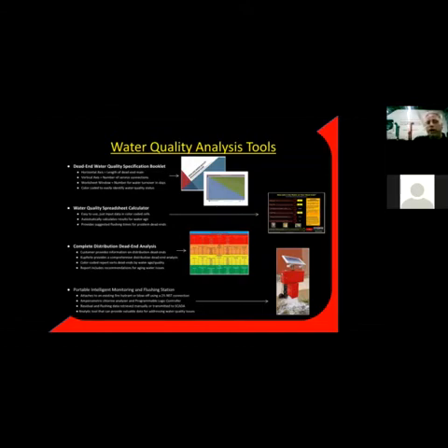The first one here at the top is a booklet. I can send one of these out to you in the mail if you like. It's a water quality booklet that basically sets up pages that you see here on the screen, where across the top of that chart is the length of your dead end in miles, from 1/10 of a mile to 5 miles long. So if I know how long the pipe is and how big the pipe is, I can calculate how much water is in the pipe.